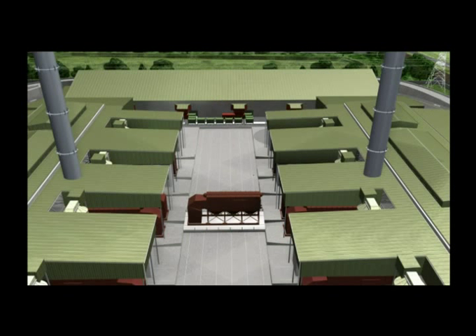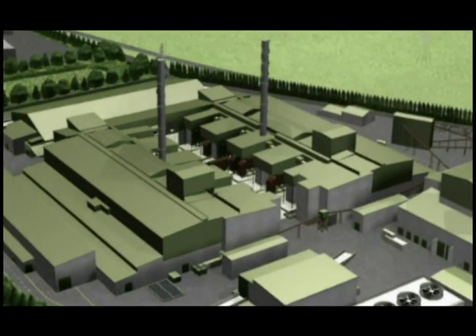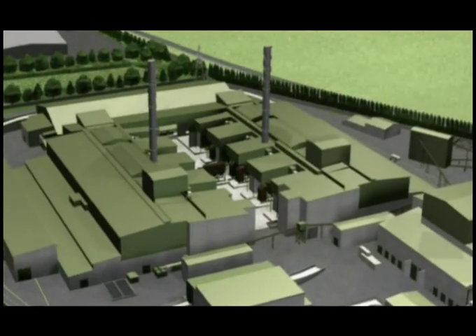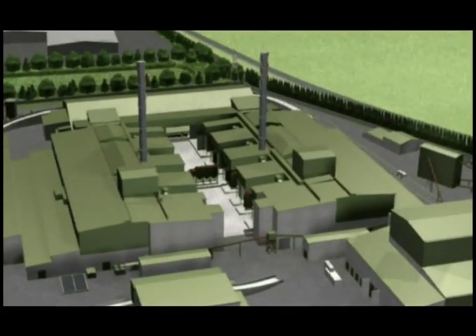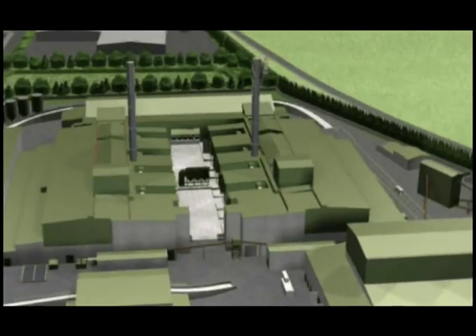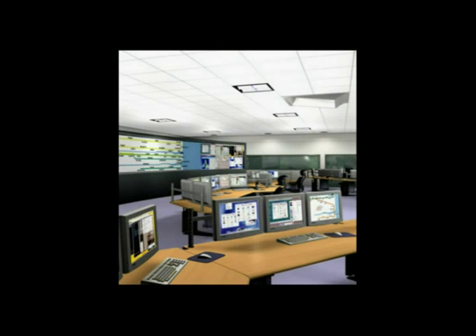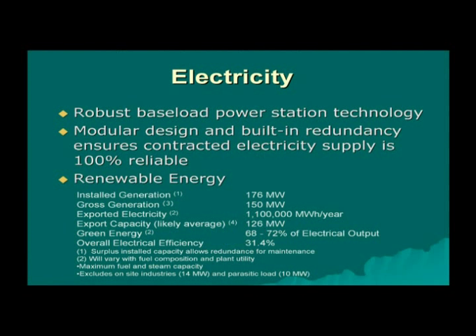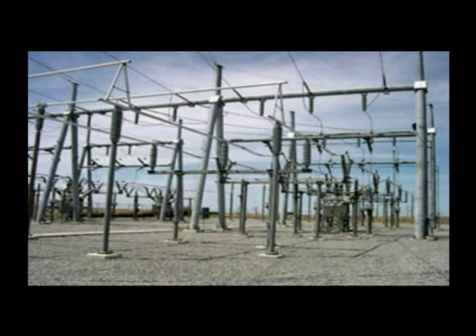Duplication of functions allows online maintenance of most functions. The maintenance of boilers and bag houses is ongoing, as there is a spare of each. They can be replaced in a few hours to allow scheduled or unscheduled maintenance. The power station is an N-1 design, which makes power generation extremely reliable and robust. This term in the power industry describes redundancy of equipment to allow maintenance without loss of production. The surplus capacity enabling this feature makes megavar correction and grid support a major feature of the plant.